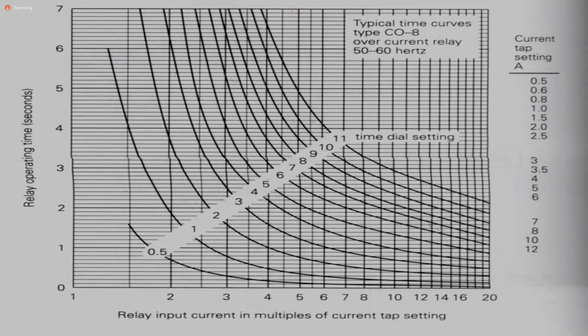Sir, he said the time dial is set at 1. So it means that we are using this curve. Right. So we're cool with that. And then he said the tap is at 8. So when we have 5 amperes coming in, how long would it take the relay to operate? 3 seconds. There are 5 amperes coming in, so how long would it take the relay to operate?